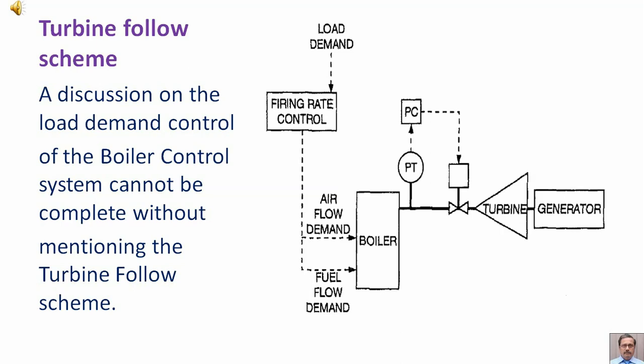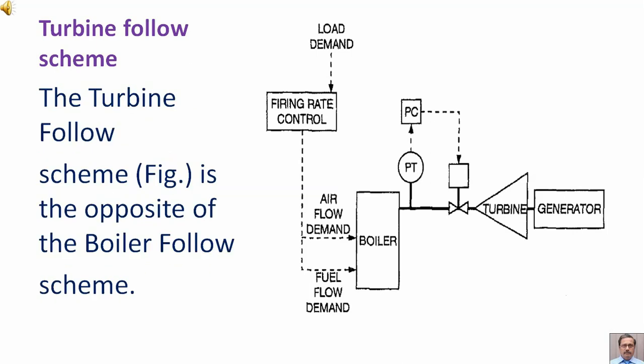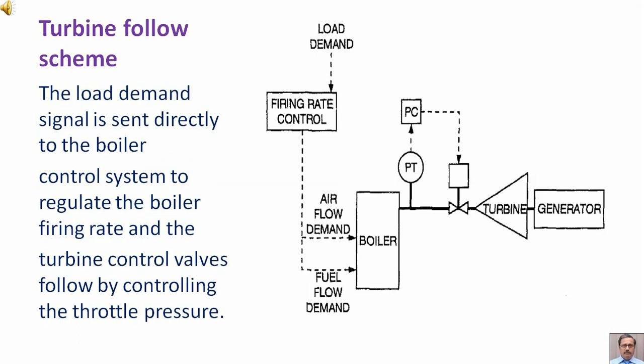A discussion on the load demand control of the boiler control system cannot be complete without mentioning the turbine follow scheme. The turbine follow scheme is the opposite of the boiler follow scheme. The load demand signal is sent directly to the boiler control system to regulate the boiler firing rate, and the turbine control valves follow by controlling the throttle pressure.